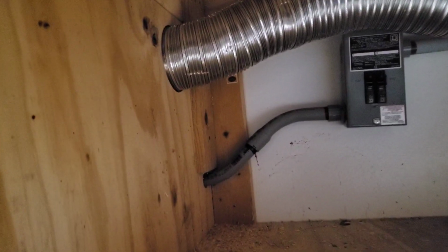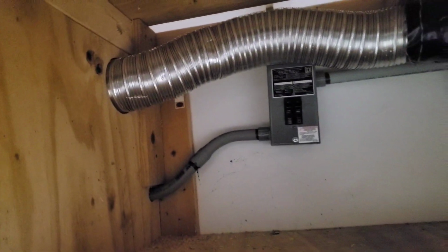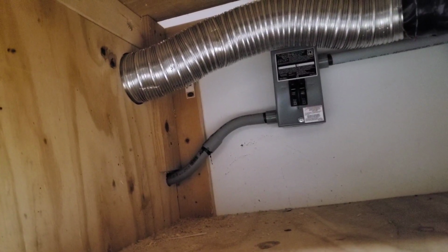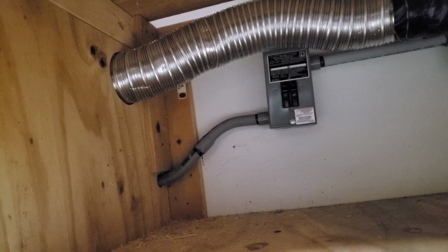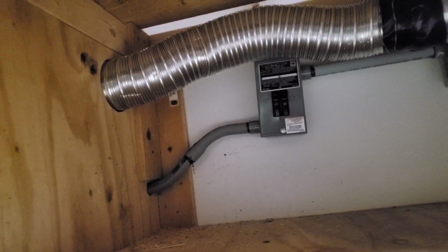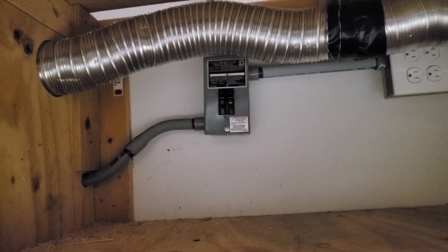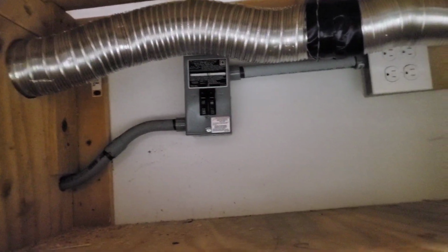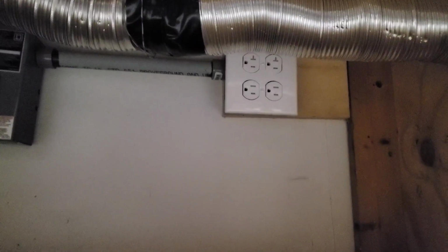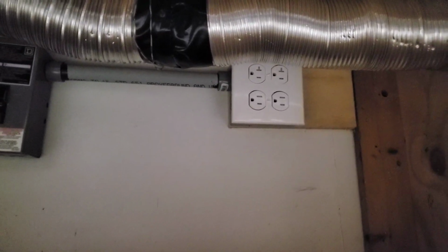And so this curved pipe coming in is actually wires coming from that 40 amp circuit, which we did tie into one hot. So there's only one hot running there. One hot, one neutral, one ground. If you're wondering what type of cable, it's called 10-2. It runs into this little breaker box, and I've got two breakers, a 15 and a 20. We've got a pair going to one of the outlets for the 15, which is the bottom outlet, and the top outlet is for the 20.